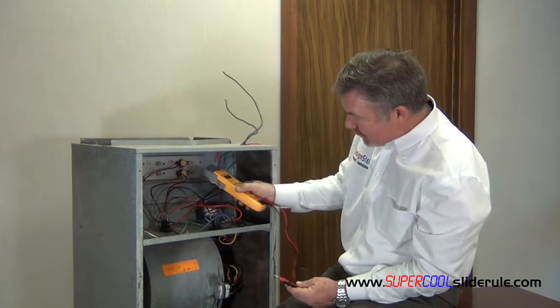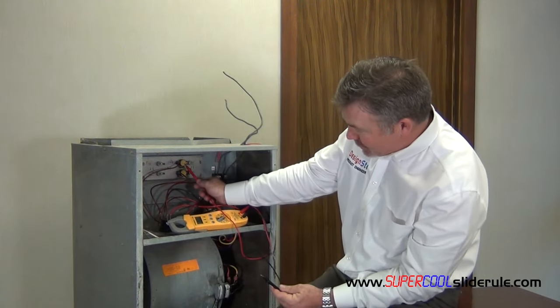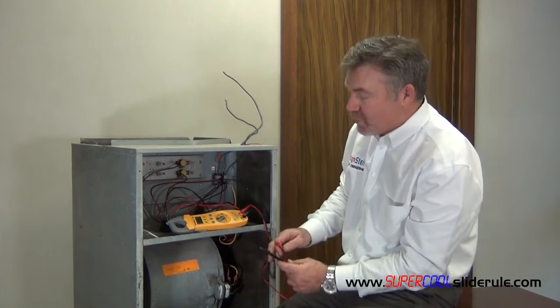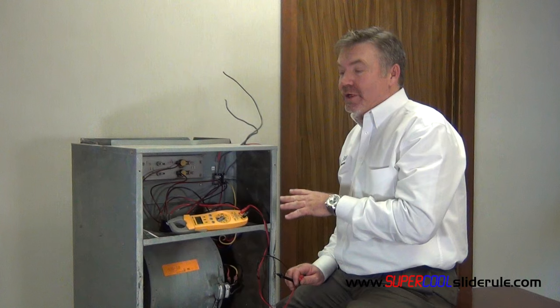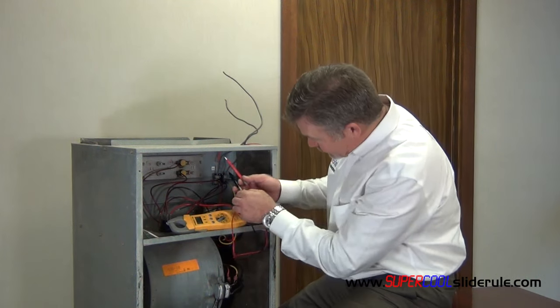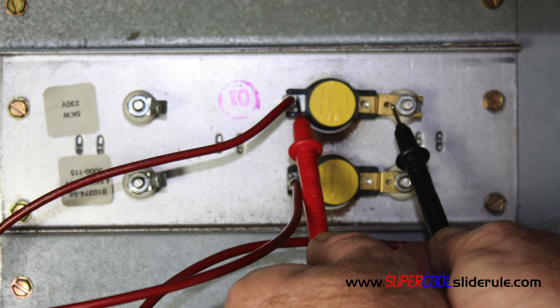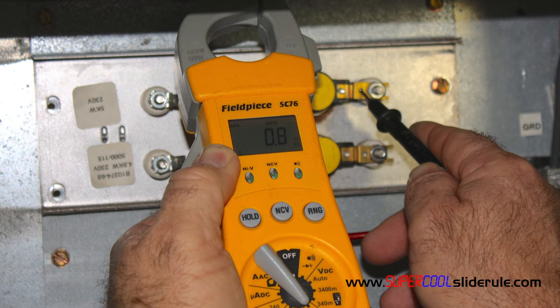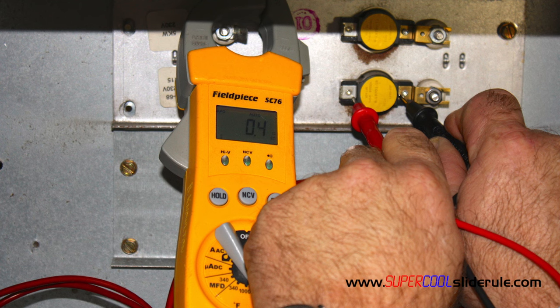What we would then do is we would then test across our limit switch. Now, the limit switch, the function of it, is it shuts the electricity off in the event that the unit gets too hot. So, we use a tester on each side of the limit switch. Our resistance should be very, very little. Here it's 0.8, 0.8 is good. Checking the one beneath it is 0.4.